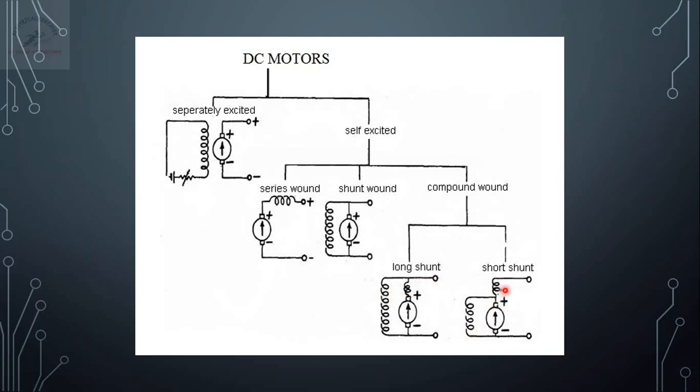An important observation: the series winding contains fewer turns than the shunt winding. In a series wound machine, the armature current flows directly through the series field, so the current is high and we don't need many turns to establish the required flux. In the shunt field, the current is less than the armature current, so we need more turns to establish the same flux. While drawing the circuit diagram, do not make the mistake of drawing equal turns — series field must have fewer turns than shunt field.